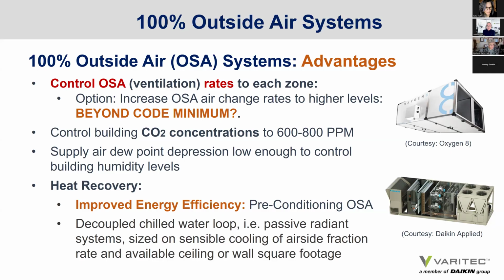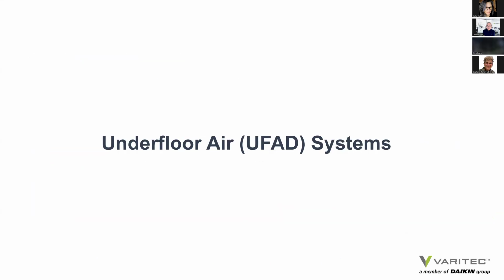So the challenge with 100% outside air systems, though, is that the outside air supplied to a building has to be properly conditioned to a low enough dew point to assume the role of humidity control in the building. It has to be dry enough to pick up the moisture gains that occur in a building, either through perimeter walls on humid days outdoors or by occupants, open sinks, toilets, kitchens, etc., anything that adds moisture to a space. And again, the advantage of an outside air system is using heat recovery as a standard option in a DOAS 100% outside air unit.